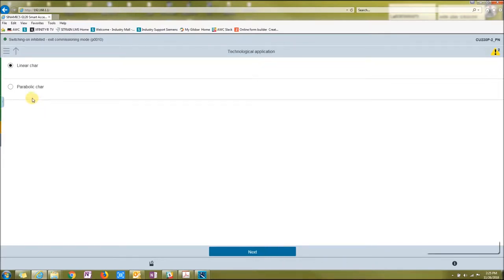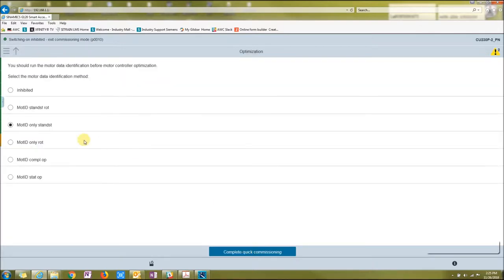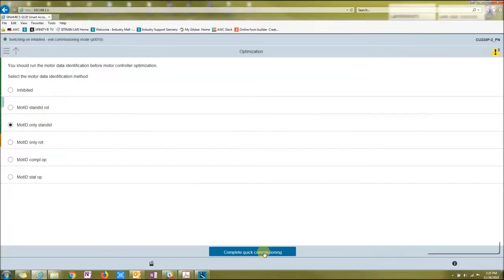Do you want linear or parabolic character? I want linear because it's multiple hertz. Do I want to start a motor ID at a standstill or rotating? You can choose any of the motor ID runs from this menu. Complete quick commissioning.